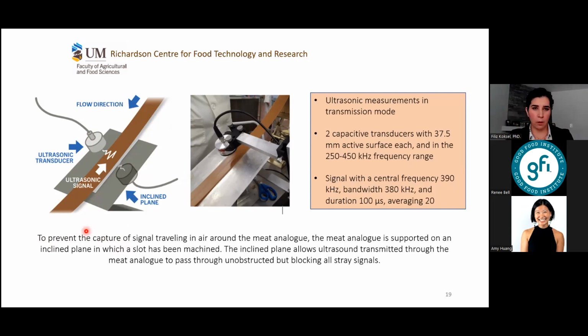So as I already mentioned, we performed the ultrasonic measurements in transmission mode. So we're getting the information from the signal that has been transmitted through the meat analog. And there are other ways to do it, for example, in the reflection mode, but we're only focusing on the transmission mode results today. And we used two transducers with active surface areas of less than 40 millimeters each. And just to give you an idea, our plant-based meat analogs were around 50 millimeters wide. So the diameter of the transducers is slightly less compared to the width of the plant-based meat alternatives. And we used a frequency range of 250 to 450 kilohertz with a central frequency of approximately 400 kilohertz.